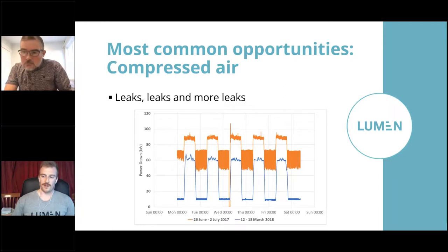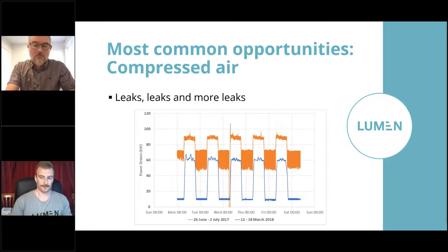There's a few ways to identify leaks. The first one is just listening. So if you switch off all the loud equipment in a factory, for example, and just have a listen for hissing, that's a really good indicator as to whether you've got significant air leaks. And that can sort of give you an idea. You can find big leaks, and you can also get an idea of how bad the situation is.